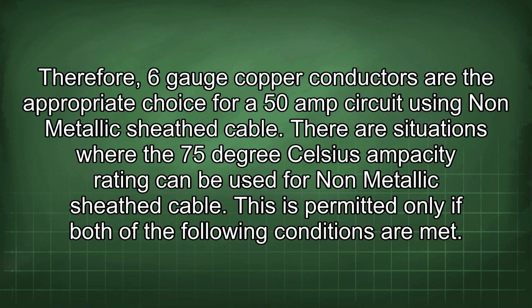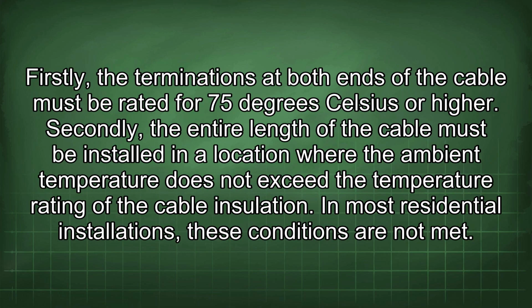There are situations where the 75°C ampacity rating can be used for non-metallic sheath cable. This is permitted only if both of the following conditions are met. Firstly, the terminations at both ends of the cable must be rated for 75°C or higher. Secondly, the entire length of the cable must be installed in a location where the ambient temperature does not exceed the temperature rating of the cable insulation. In most residential installations, these conditions are not met.